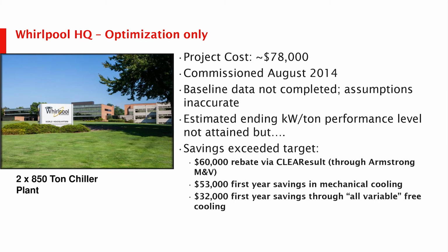So one chiller runs 60% of the time, and when we want parallel operation, we run chillers 2 and 3. That's just the only way it's going to work. So they have a disproportionate number of run hours on that one piece of equipment, and it's going to be like that until they eventually pay to fix it.